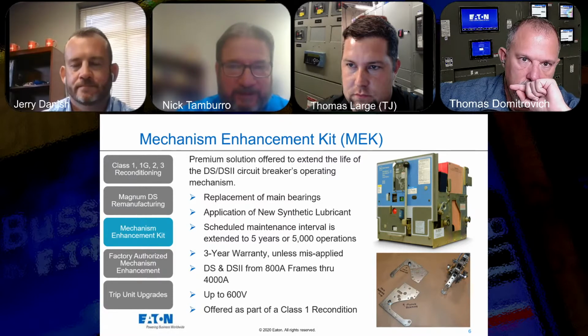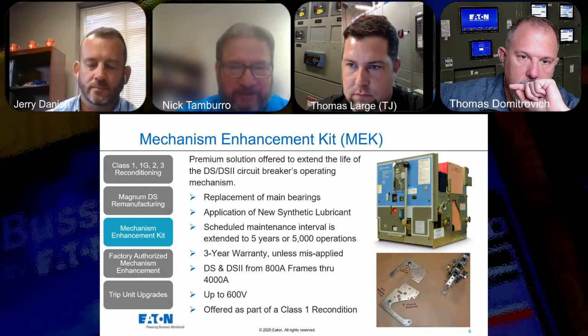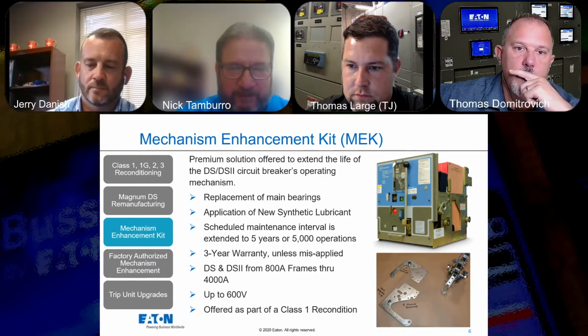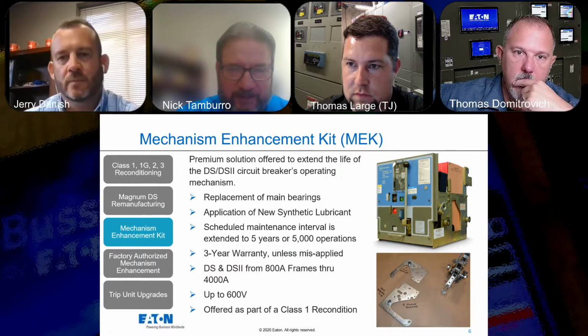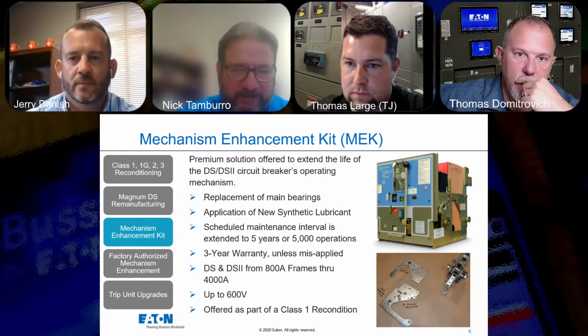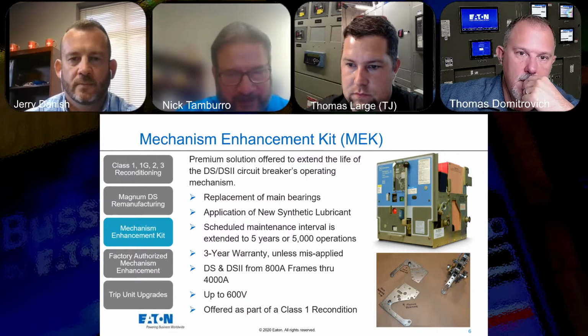If people put a breaker in the cell, close it, and leave it closed for a year, things kind of gum up in there. That's what that sounds like, the grease is gummed up. Spraying some kind of lubricant in there might be enough to free it up, but eventually it's going to bind again.